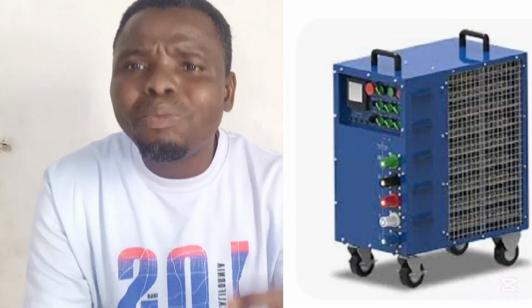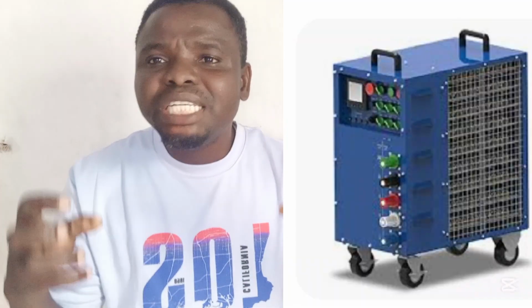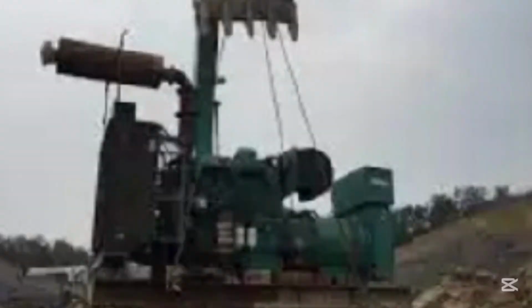So what is the solution? If it's a generator, ensure you run it on load bank testing. The load bank testing will ensure that the generator is stressed, works harder than usual, and that will ensure that your exhaust line stays dry.